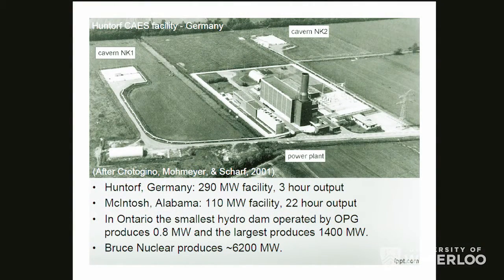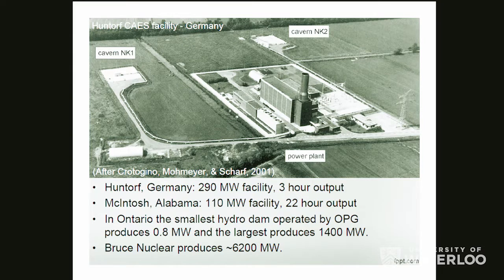As we were talking about the Huntorf CAES facility in Germany — this is a picture of it above — it's a 290-megawatt facility rated for three hours of power production. You can see the two cavern wellheads at the top and the facility itself below. The other example Maurice mentioned was the McIntosh, Alabama facility, which is a 110-megawatt, 22-hour rated output facility. To give you a scale, in Ontario, OPG operates hydro dams ranging from 0.8 to 1,400 megawatts, and the large nuclear power plant generally produces 6,200 megawatts.